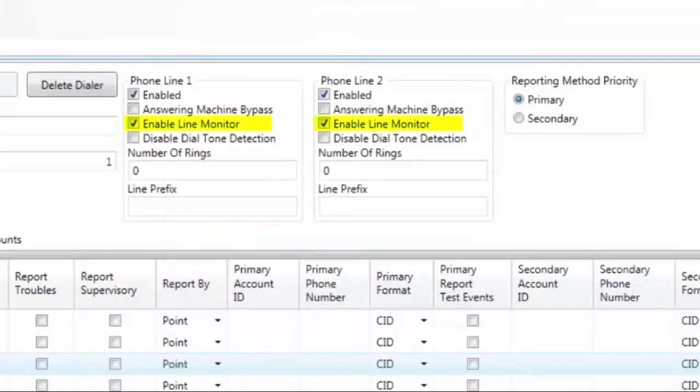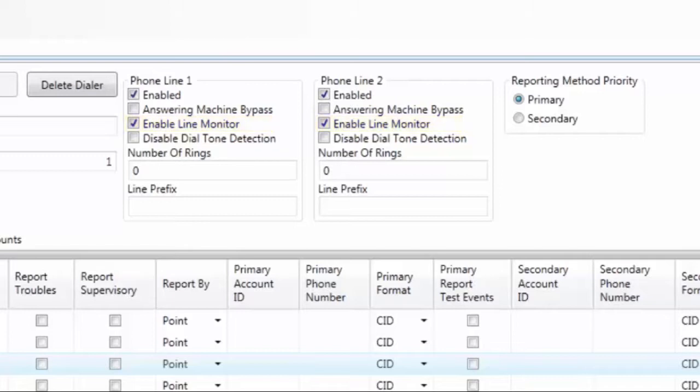The next setting for the phone line is Enable Line Monitor. The default is Check. When this box is checked, the UD1000 is monitoring the phone lines for 15 volts plus or minus 5 volts. If, for some reason, the connection that is being used does not have voltage on it, you can uncheck the box so the UD1000 will not monitor for voltage.